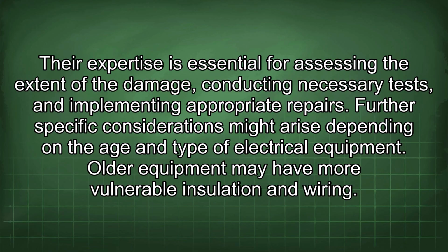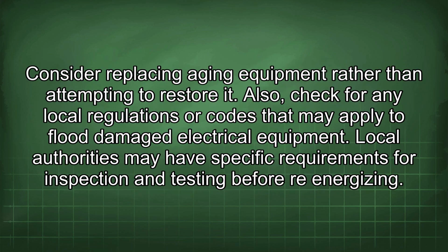Further specific considerations might arise depending on the age and type of electrical equipment. Older equipment may have more vulnerable insulation and wiring. Consider replacing aging equipment rather than attempting to restore it. Also, check for any local regulations or codes that may apply to flood-damaged electrical equipment. Local authorities may have specific requirements for inspection and testing before re-energizing.